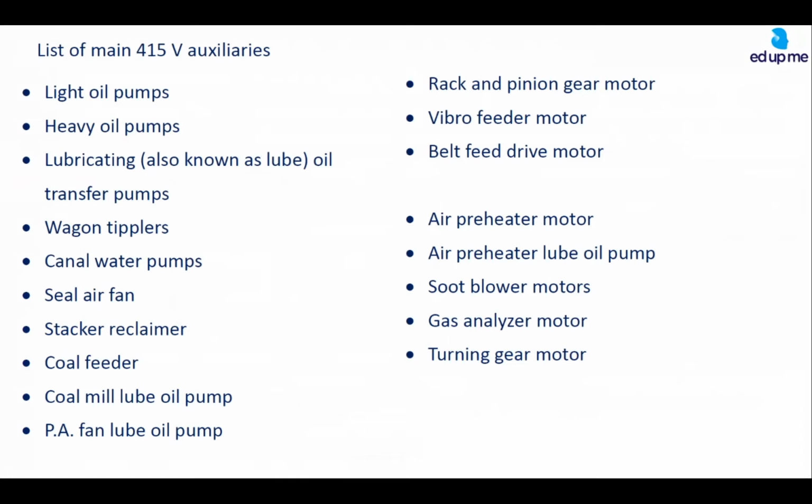I mean, the complete water tube walls have to be cleaned periodically. While the boiler is on load, when the unit is working, soot blowing is done by dry steam. For that, there are many soot blowers, some 56 soot blowers throughout the different elevations in the boiler, and there are long retractable blowers. That needs power, as do the gas analyzer motor and turning gear motor.